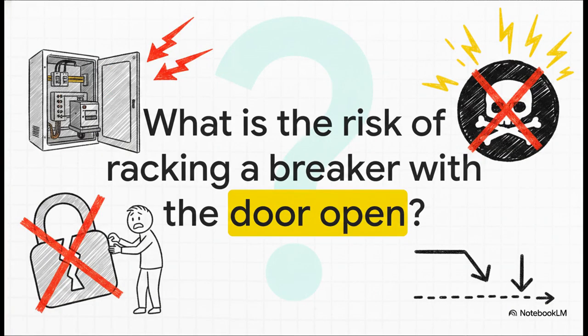So, what actually happens when a violent arc fault ignites right behind that metal door, with a technician standing just a foot away? Consider this very real scenario. A tech wants to rack a breaker out with the compartment door open, deliberately bypassing the interlock just to, quote-unquote, save some time. What is the actual risk here? I want you to seriously think about the massive safety implications of deliberately ignoring the board's built-in physical defenses.